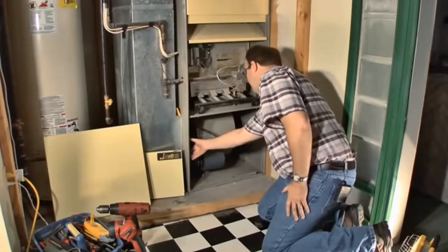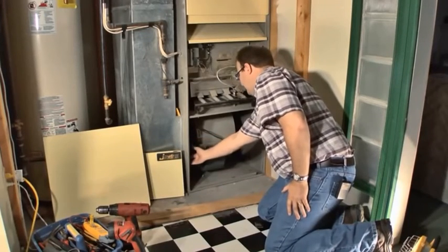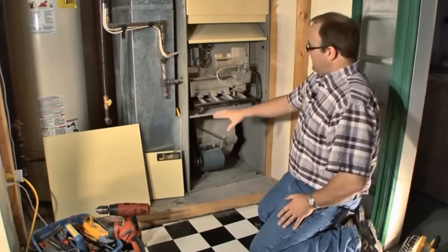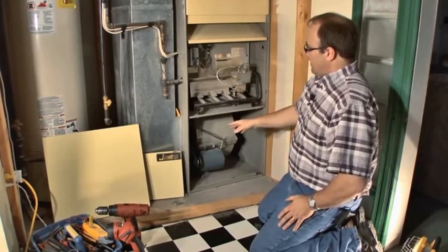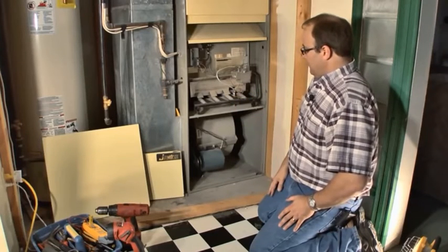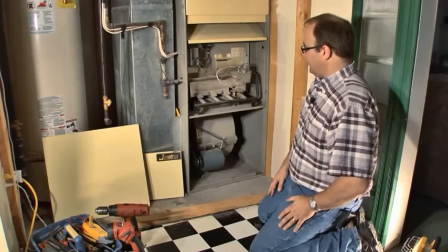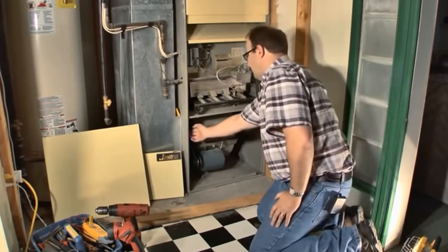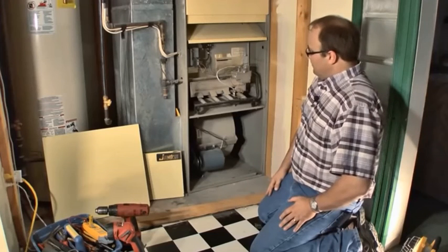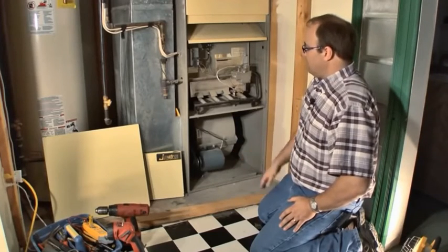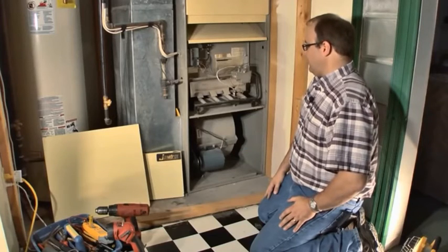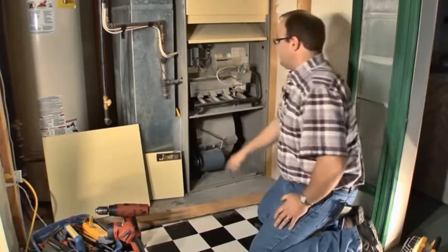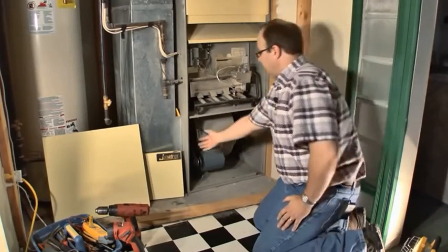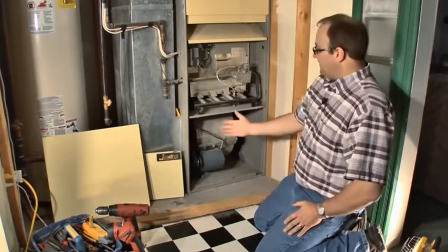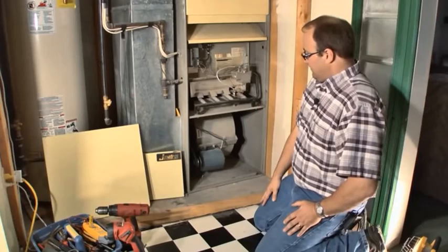Okay, I reinstalled the bracket that holds the filter in, and I did reinstall the dirty filter. The reason I want to show what the heat rise is, is that it's one of the diagnostic things we measure to see how efficient the furnace is and how much air we're moving through it. The key is to move as much air as possible, and a high heat rise is usually caused by a dirty filter or too small of a ductwork. Anything that restricts airflow gives us a high heat rise. So a dirty filter should show us a high heat rise. I reattached the bracket and screwed it on so that shouldn't happen again, where the filter gets sucked into the blower.